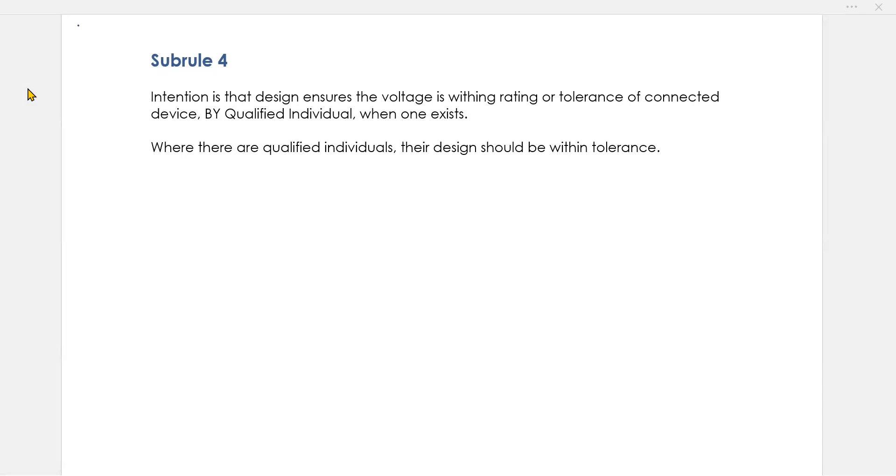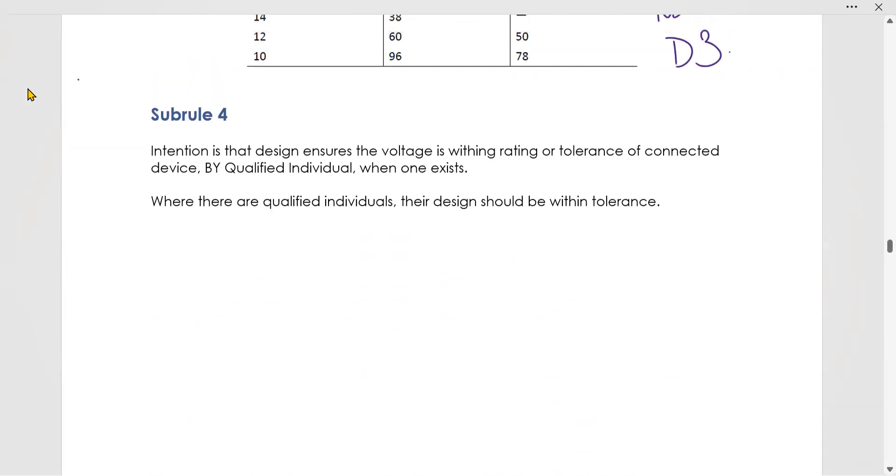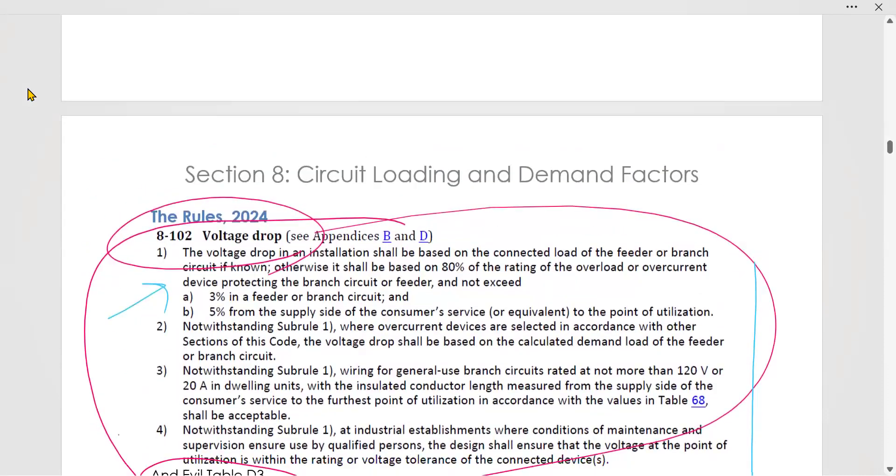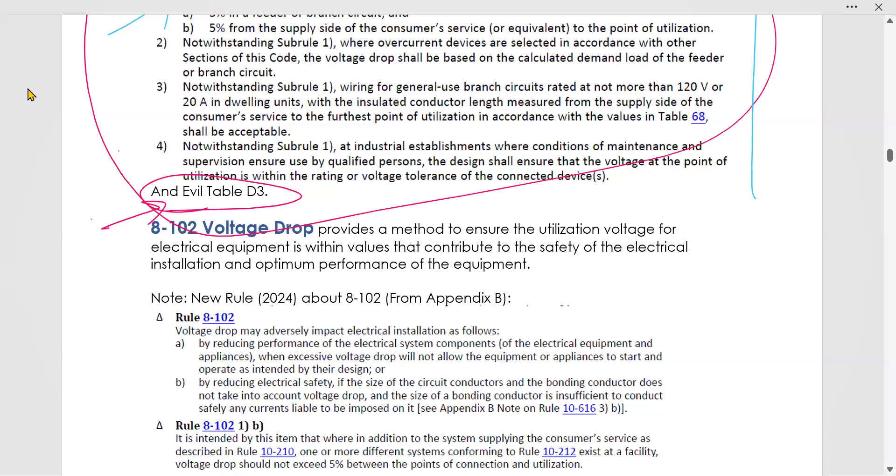Subsection, subrule 4 says that intention is that design ensures the voltages within rating or tolerance of connected device by a qualified individual when one exists. Where there are qualified individuals, their design should be within tolerance. So basically, subrule 4, let's see how it's actually worded in the rule. It says, notwithstanding subrule 1, at industrial establishments where conditions of maintenance and supervision ensure use by qualified persons, the design shall ensure that the voltage at the point of utilization is within the rating or voltage tolerance of the connected devices.